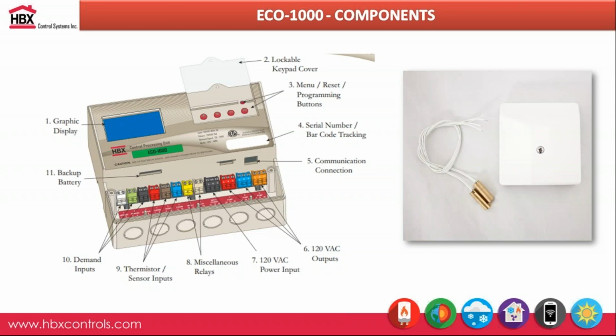And then we have 3 120 volt outputs on there to control your pumps. So you can control up to 2 pumps. The last relay on the Eco 1000 is going to be to control your reversing valve, which you need to accommodate a relay in there to bring that down to 24 volts, because normally those reversing valves or diverting valves require 24 volts to power them.